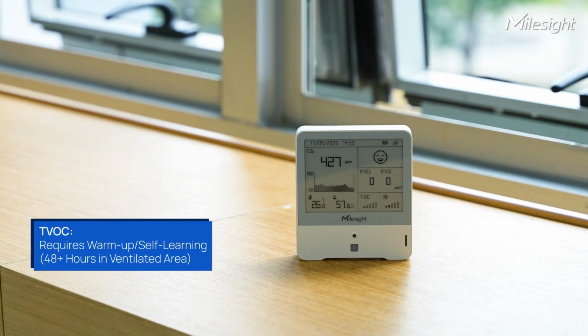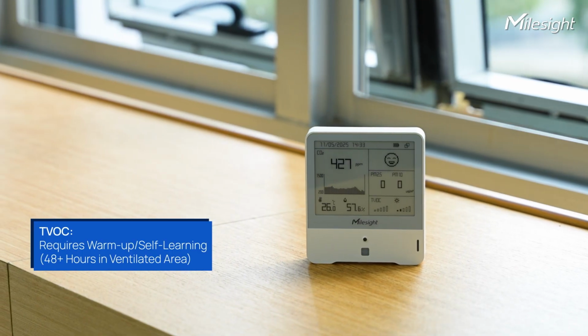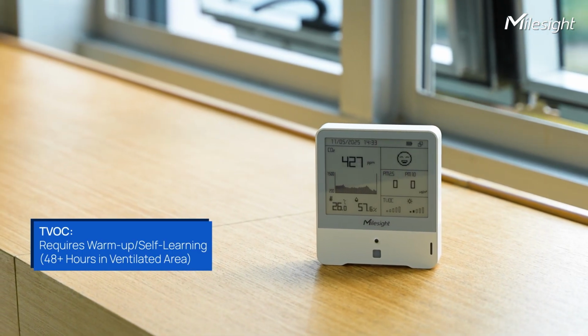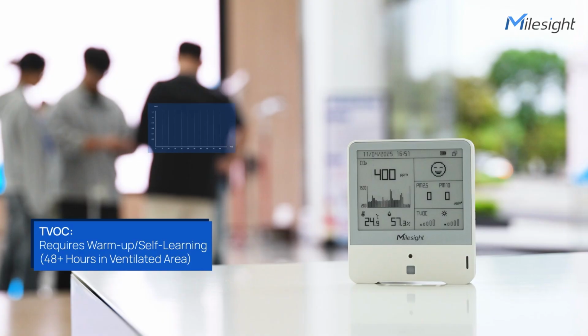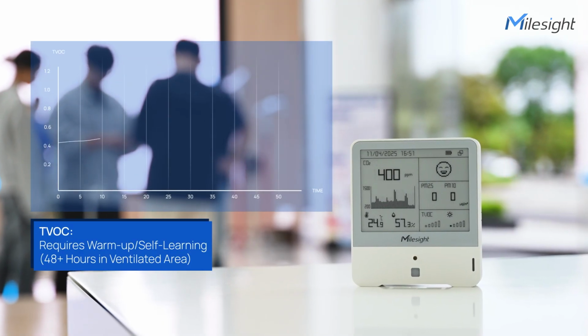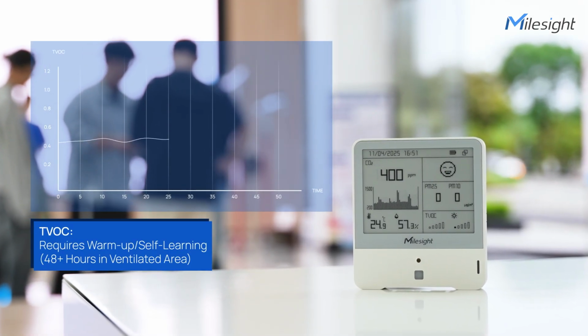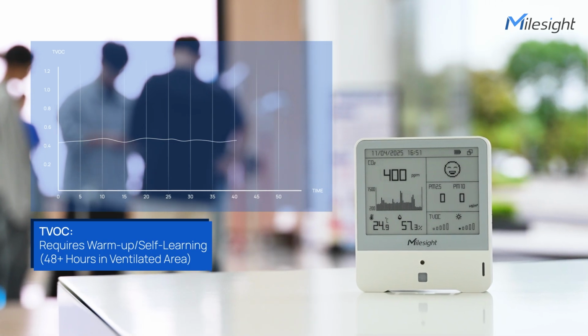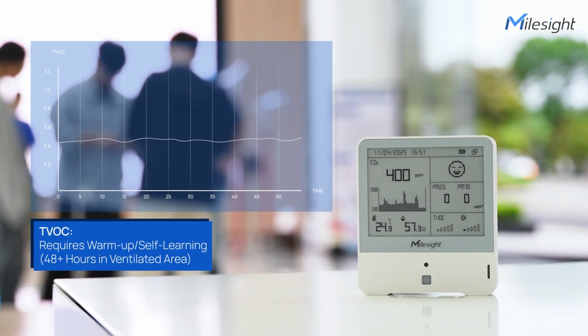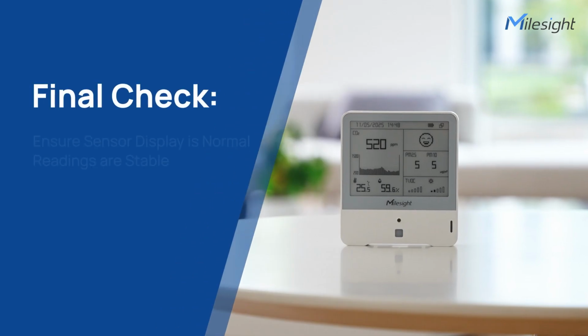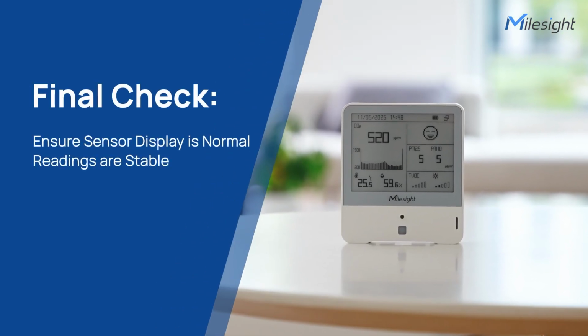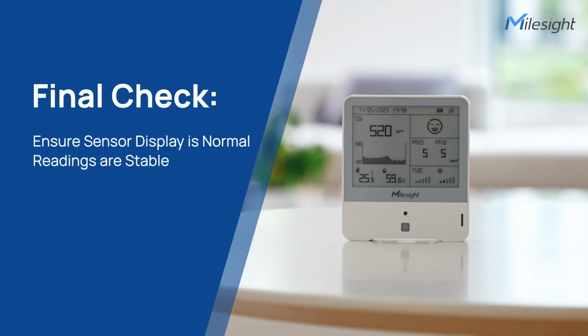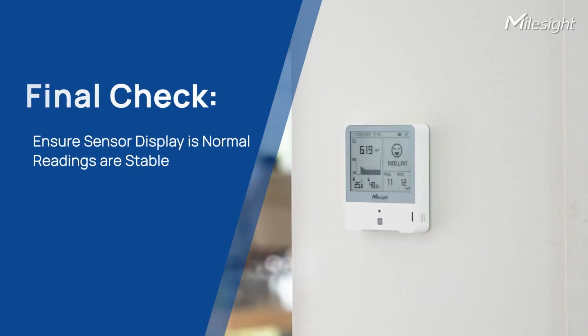If your device is an AM300 series model, please note that the TVOC sensors require a warm-up and self-learning process after first power on. Ensure the device automatically acquires the environmental baseline value in a well-ventilated environment for 48 hours and do not turn it off during that time. Finally, ensure the sensor screen display is normal and all parameter readings are stable after initialization and calibration.